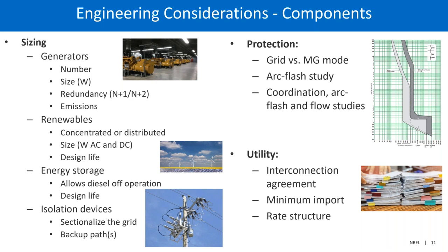Protection is another big piece of the engineering design. This has to do with looking at how you protect the system in case something happens on the system, like a branch falls across the line. And it's very different to protect it when it's tied to the grid versus when it's in microgrid mode.